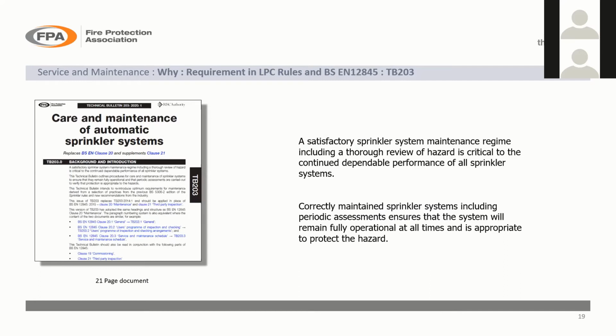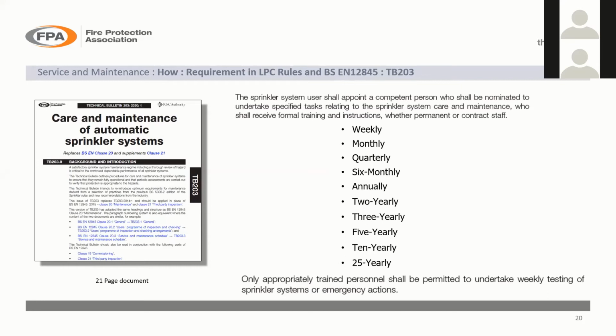So a correctly maintained one, including the periodic assessments, ensures that the system will remain fully operational at all times and is appropriate to protect the hazard. So it sets out the stall there that the system does need to be maintained, and then it goes into quite a bit of detail as to how to do it. I am pressing on quite quickly.